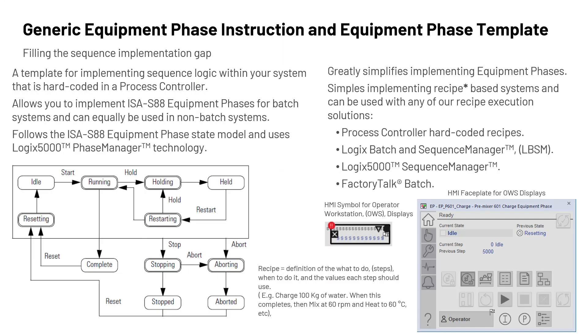The generic equipment phase instruction and equipment phase template fill the sequence implementation gap. They provide a template for implementing sequence logic within your system that is hard-coded in a process controller and they are only available to use in a process controller. It allows you to implement an ISA S88 equipment phase for batch systems and can equally be used in non-batch systems.